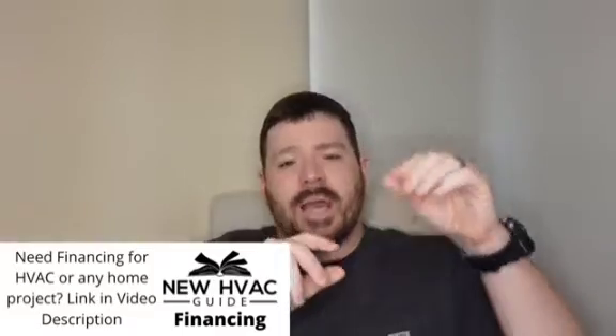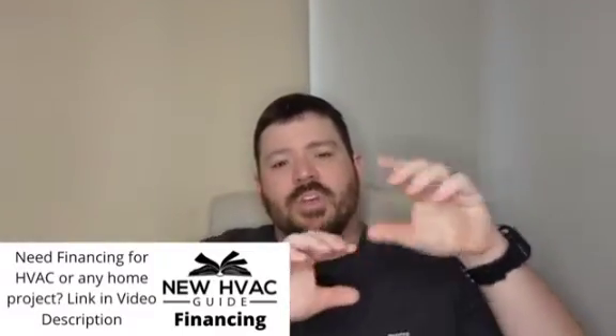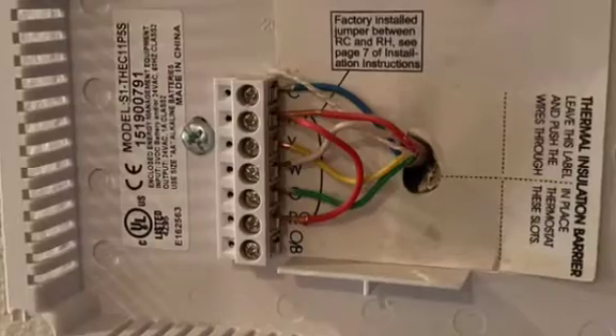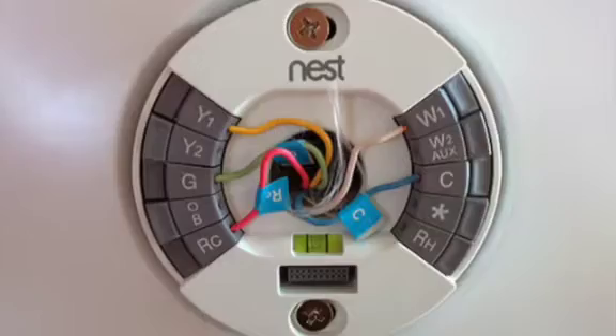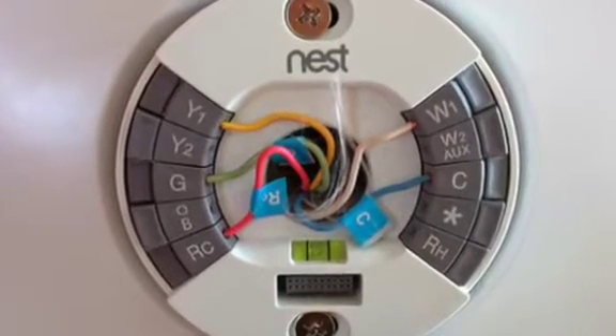Number 25, let's talk real quick about what I would call the pinch tabs or the screws of thermostats. And the reason I wanted to touch on this is if you have screws that need to be tightened down on the wires themselves, you've got a terminal block, you want those screws to be tight. But I'm seeing where folks are installing these pinch tab thermostats. It's kind of the new thing. A lot of the big brands have them on their newer thermostats. Nothing wrong with them if they're installed properly.